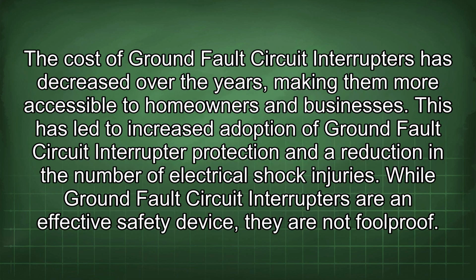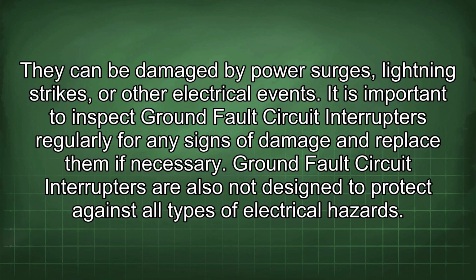The cost of ground fault circuit interrupters has decreased over the years, making them more accessible to homeowners and businesses. This has led to increased adoption of ground fault circuit interrupter protection and a reduction in the number of electrical shock injuries. While ground fault circuit interrupters are an effective safety device, they are not foolproof. They can be damaged by power surges, lightning strikes, or other electrical events. It is important to inspect ground fault circuit interrupters regularly for any signs of damage and replace them if necessary.